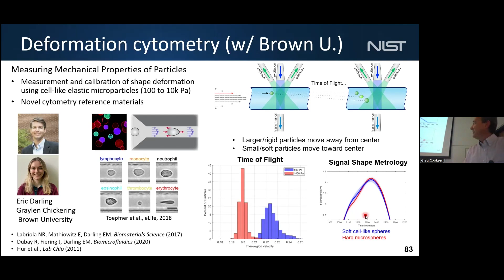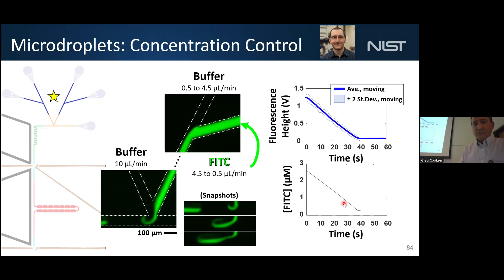We're also putting droplets in these devices, so we are now controlling the concentrations of dyes and substrates to create reactions in droplets. This is a nice system because now by controlling the concentration of the fluorophore, we can actually use this to calibrate the measured fluorescence intensity of our cytometer. Normally you have to do that with plastic particles, but again, those particles are embedded in a matrix, and does that matrix give you the true fluorescence intensity of a dye bound to a cell? It's unknown. So here we have the ability to calibrate to fluorescence intensity, and we can scan through these different concentration distributions from a full gradient within a minute.